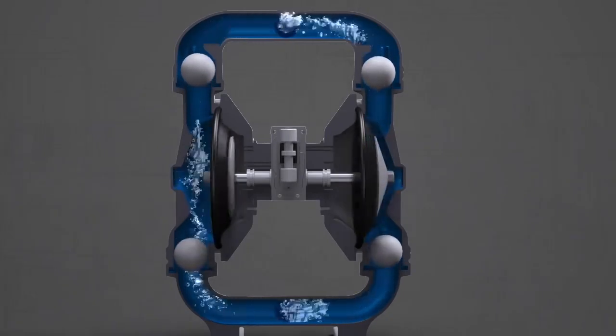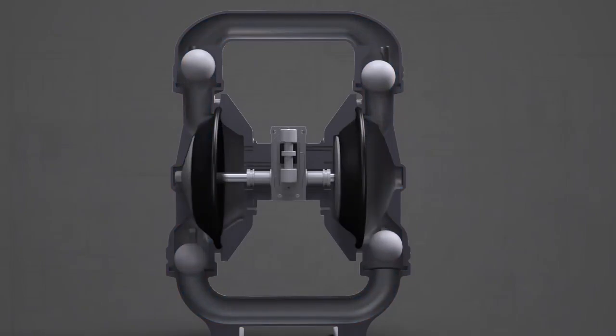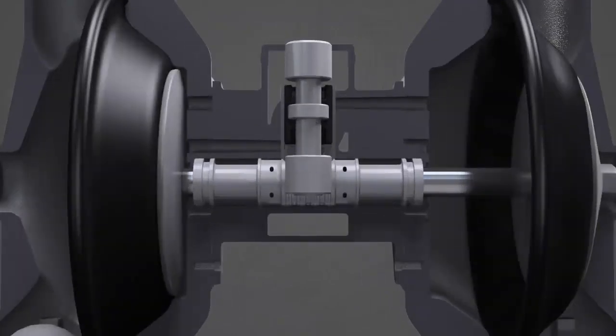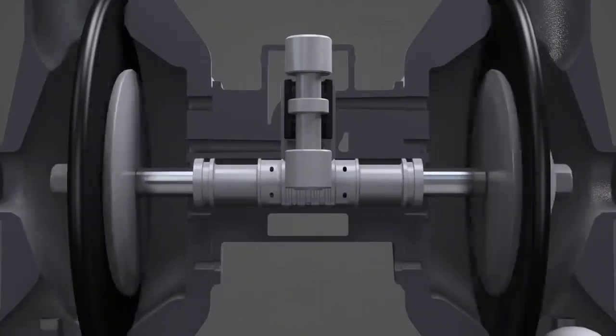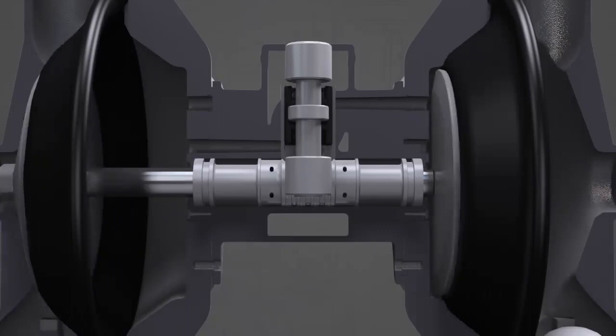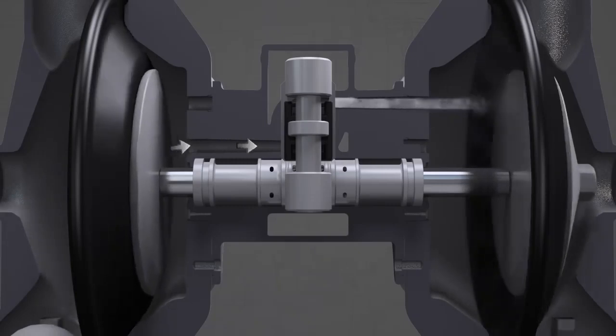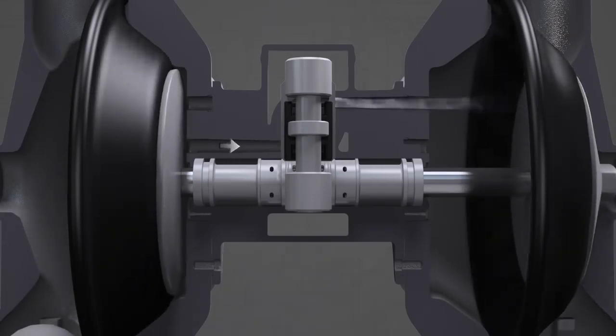The pump diaphragms are driven by pressurized air that is directed left and right by the movement of the main air valve. Here's how it works. When air pressure is applied to the pump, the main air valve moves up and down. When the main air valve is in the down position, air pressure is diverted to the right diaphragm. At the same time, exhaust air from the left diaphragm passes through the shuttle and shuttle plate and exits the rear of the pump.